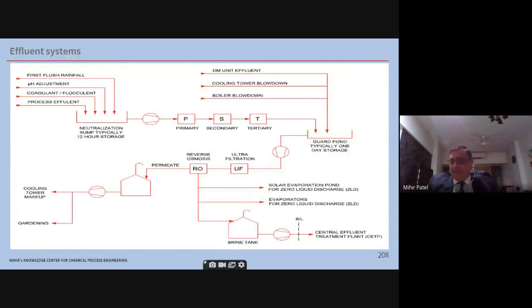Effluent systems. Now, effluent systems are very important. Nowadays, the Pollution Board has got very, very strict on this. So here, if you see on the left, this entire plant is basically an ETP plant. First pit you have is a neutralization sump, where you have the first flush of rainfall coming. This first flush of rainfall is nothing but the first 15 minutes of rainfall. This basically cleans the ground. The ground may have some contaminations of oil, chemicals. So that first flush is taken to this tank, so that you don't directly divert it to storm water. After 15 minutes of rainfall, that rainfall can be diverted to storm sewer because it's clean water.